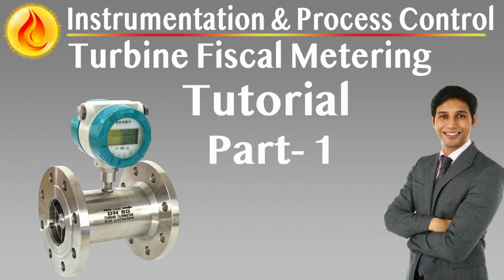Manufacturers are required to submit comprehensive procedures that include calibration strategies, validation sequences, and decision-making logic for when and how adjustments should occur. These procedures must be transparent, auditable, and compliant with custody transfer regulations. Importantly, no adjustments to any component are permitted unless its calibration error exceeds predefined limits. This strict policy avoids unnecessary interference and preserves traceable calibration records.